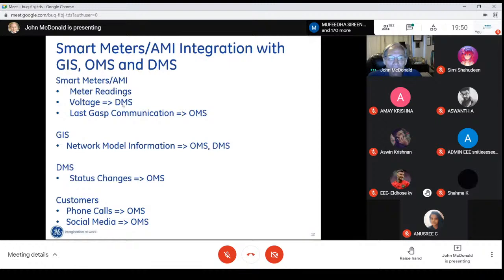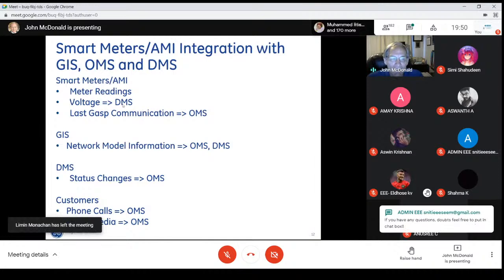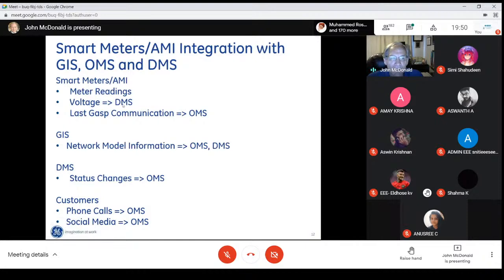But we have to make sure the voltage at the very last customer is within the limits. Every country has a standard with respect to what the voltage should be at the customer. In the United States, it's 120 plus or minus 5%. It's an ANSI standard, American National Standards Institute, ANSI standard C84.1 in the US. So 120 volts minus 5% is 114 volts.